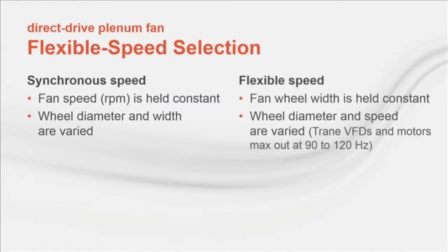Flexible speed selection is a relatively new concept in the industry. With this approach, the width of the fan wheel is held constant, and the diameter or speed of the fan is then changed to achieve the desired performance.